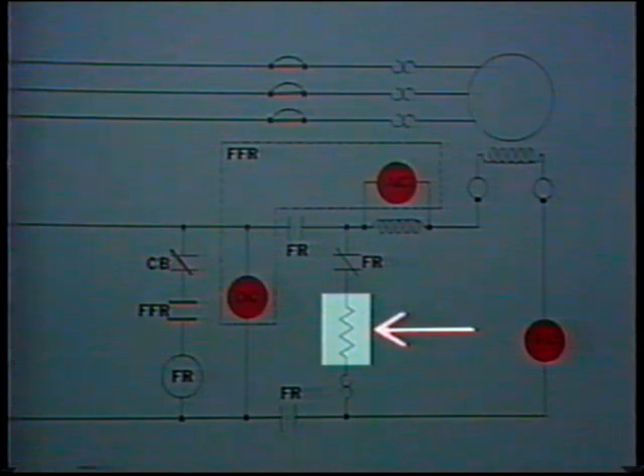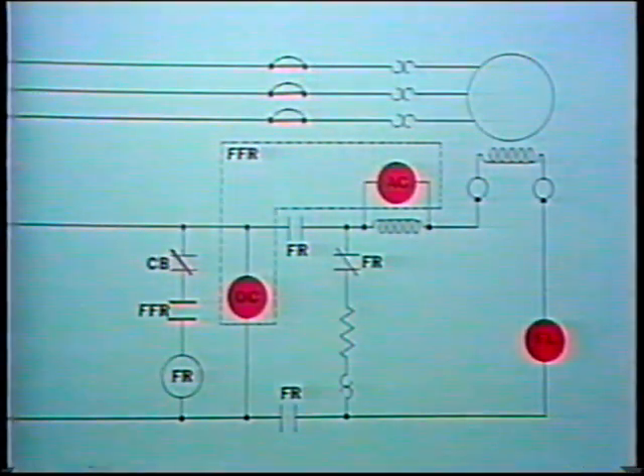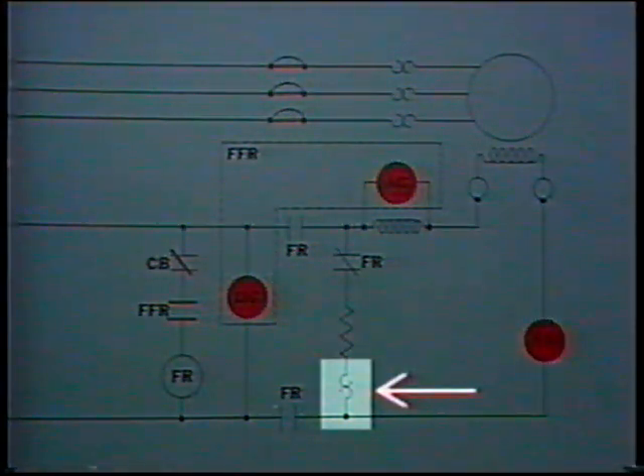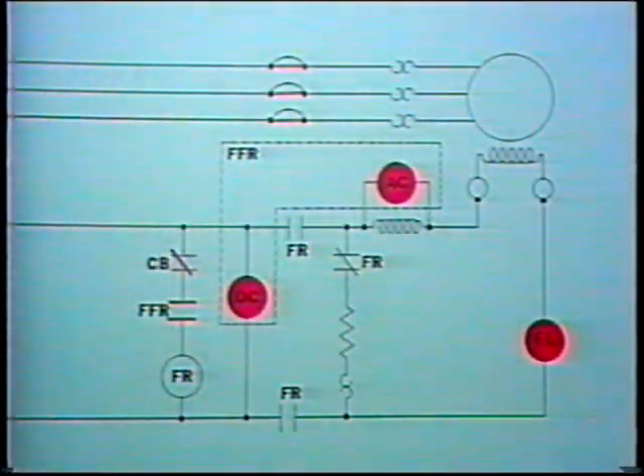Resistors in this part of the circuit are used to limit the amount of alternating current flow. If the resistors were not placed in the circuit, alternating current flow would increase to the point where it would burn wires or cause damage to the insulation of the wires. Another component of this part of the circuit is a heater element for a thermal overload device. The heater element senses the amount of current flow through the circuit and is designed to open the circuit breaker if current flow persists for too long.